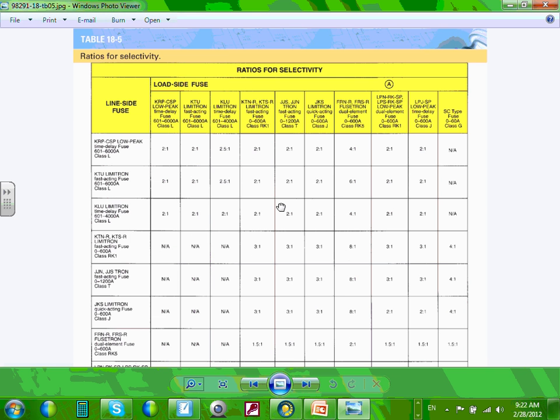Take this. If you want fuses, guys, to coordinate fully with each other, here's the rule for fuses most of the time. Most of the time. So Rob, if I want to guarantee coordination between 2 fuses or 2 circuit breakers, for the most part, if you make the feeder no more than half of the main, you're almost coordinated. Take this. That's a rule of thumb.